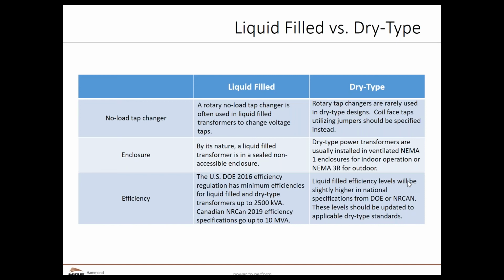Efficiency, there are different efficiency levels for liquid-filled versus dry type. The efficiency levels for liquid-filled, actually not generally, always for liquid-filled, will be a little bit better, a little bit higher than the dry type. And we've addressed that earlier.